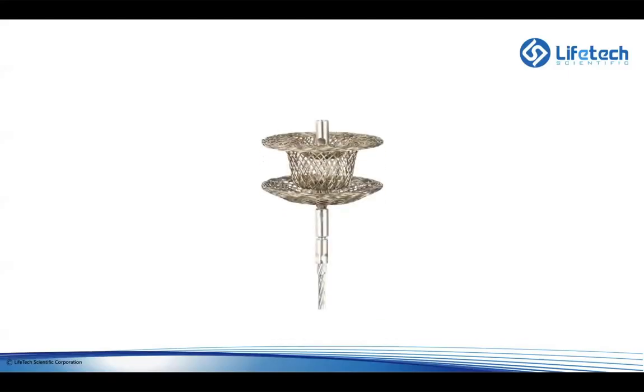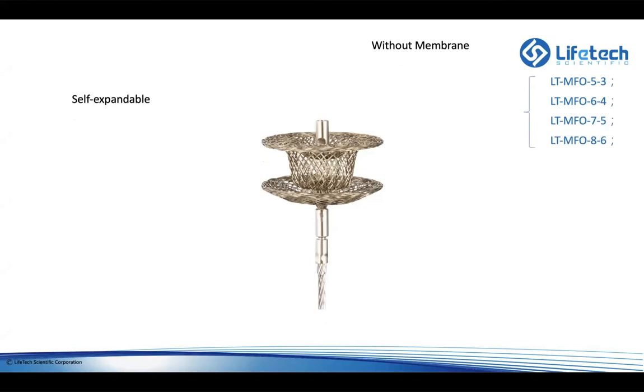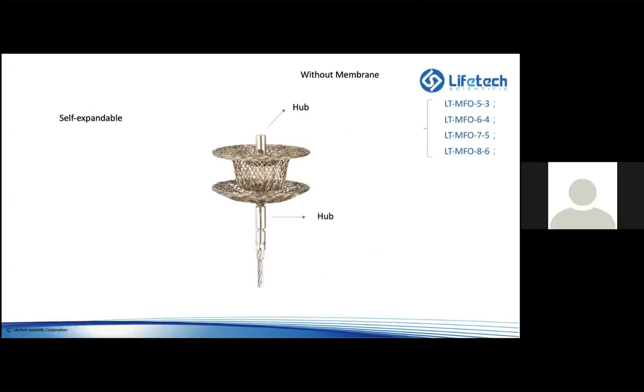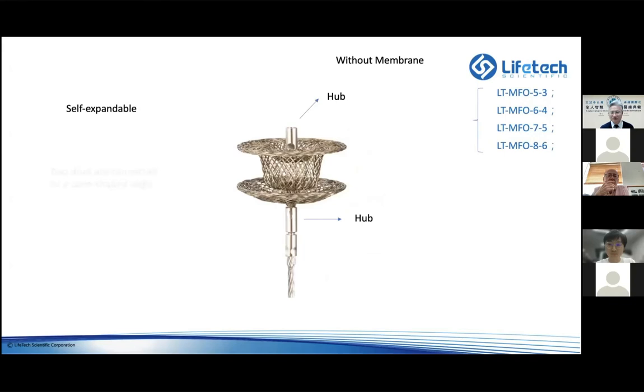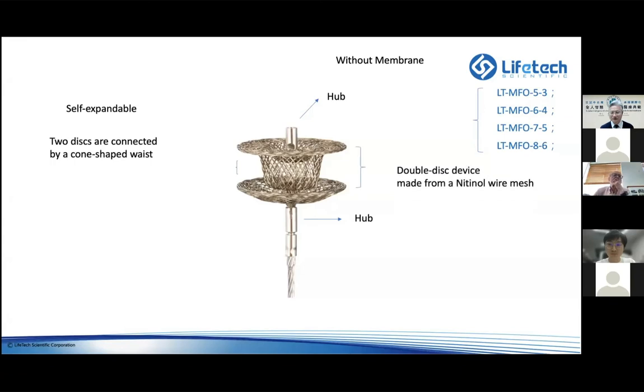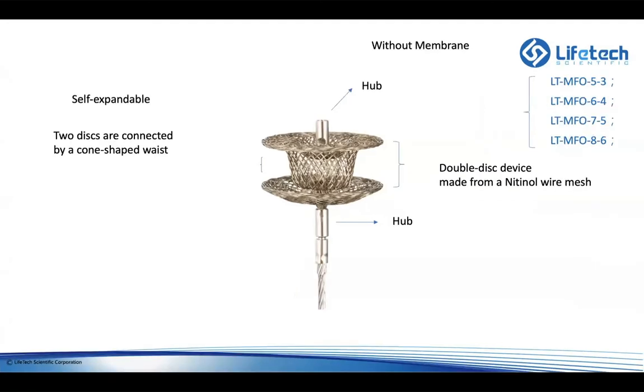So first of all, I thought I'd just go through the device itself. This is the device, as you can see. It's a self-expandable nitinol frame. The smaller devices, the 5.3 through to the 8.6, they don't have a membrane. You can see there, it's just the frame itself. It has two hubs, and that's a huge advantage of this device. So you can deploy it from either a left ventricular approach or a right ventricular approach, depending on what your concerns are and where the defect is and what's going to be the easiest path through. And there's two discs connected by a cone-shaped waist and a small connection between the two retention discs on each end. It's a double disc device, and as we said, nitinol wire mesh.